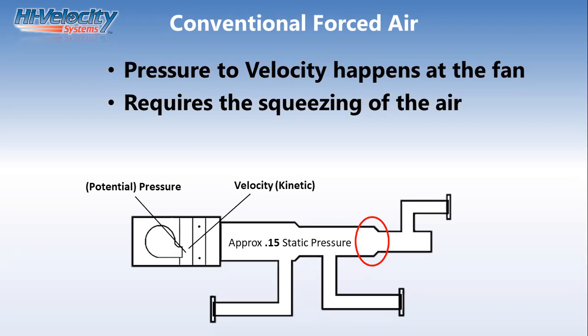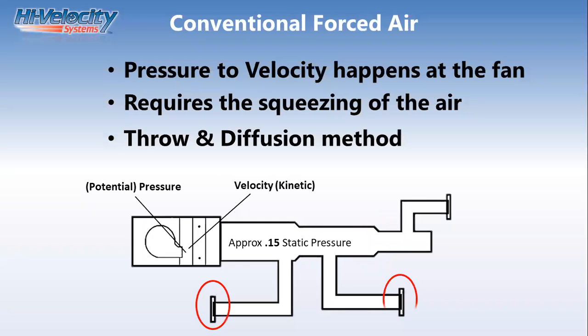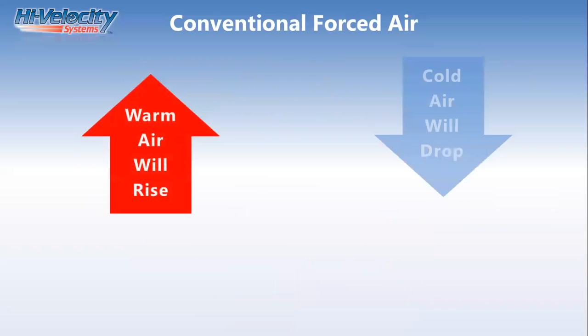We have to add balancing dampers to ductwork, and we have to virtually trick that airflow to get to the furthest outlets in that home, often requiring at times things like booster fans, balancing dampers. At the termination point, when the airflow enters the room, it uses the throw-and-diffusion method of air delivery, trying to divert that airflow in multiple directions in the hopes that by doing so, you're going to create a stirring of the room air and mix those heated and cooled BTUs throughout that space.